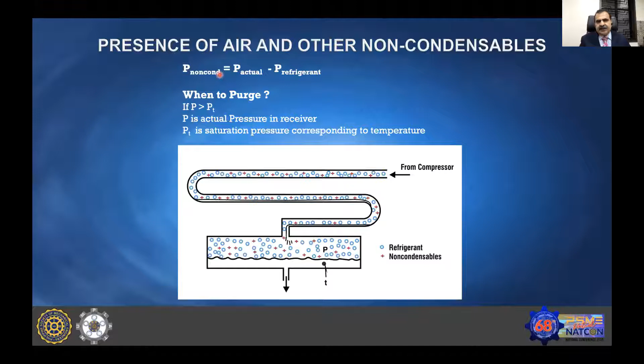That kind of pressure difference directly affects our refrigeration system, and the difference indicates the presence of non-condensable gases. What happens with non-condensable gases is that because they are free bodies, they do not contribute to any refrigeration effect, and this non-condensable gas or air keeps on moving with the ammonia gas from the evaporator to the compressor and from the compressor to the condenser. It increases the electrical power demand and reduces refrigeration efficiency because it keeps occupying space, decreasing overall system efficiency because our required power is more than the actual refrigeration effect achieved.